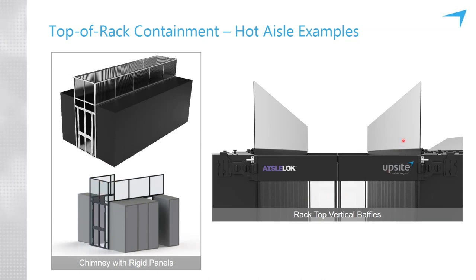This is that baffle solution applied to a hot aisle where the baffles are now vertical, just to direct the hot air vertically and prevent it from prematurely rolling over the cabinets. And this directs it vertically up to the ceiling registers so the hot air can return to the cooling units.